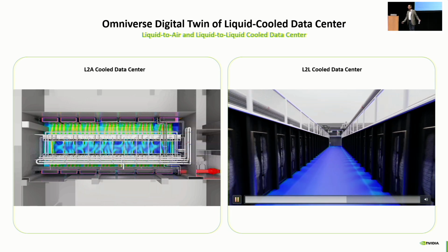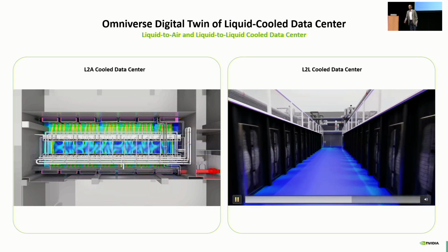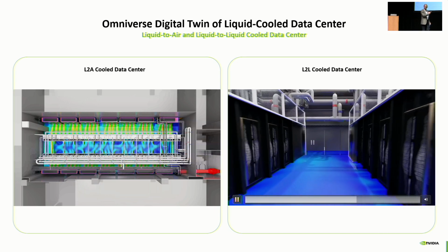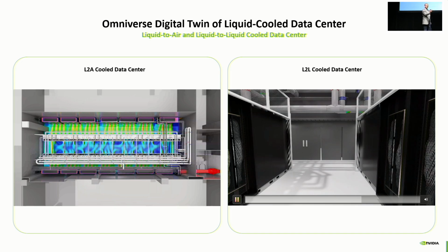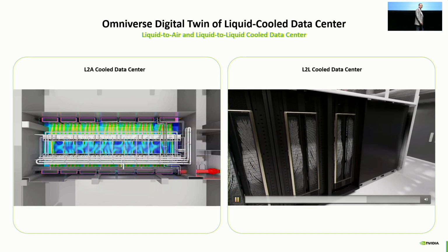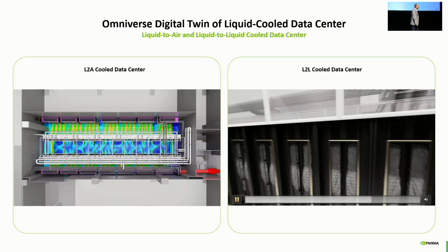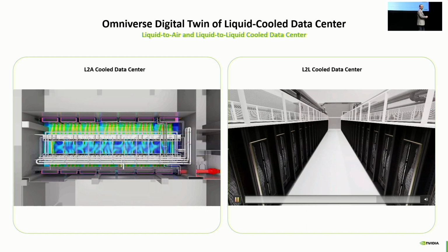So if I have a 130 kilowatt rack, I have about 120 kilowatts that I can remove with one CDU, and many rows of these racks, with residual heat being removed by the CRAH units.